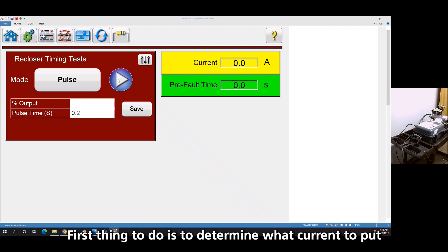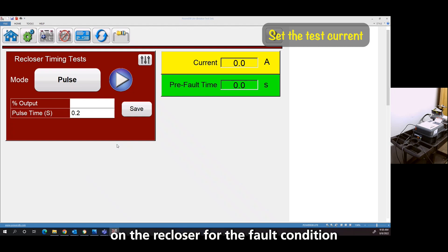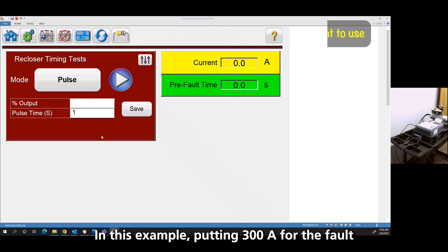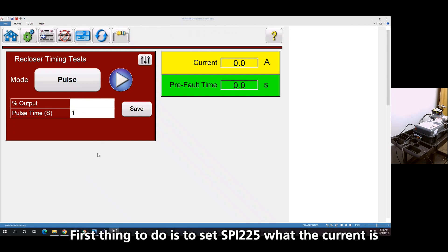The first thing you have to do is determine what current you want to put on the recloser for the fault condition. Since it was set at 100, I want to put 300 amps for my fault.